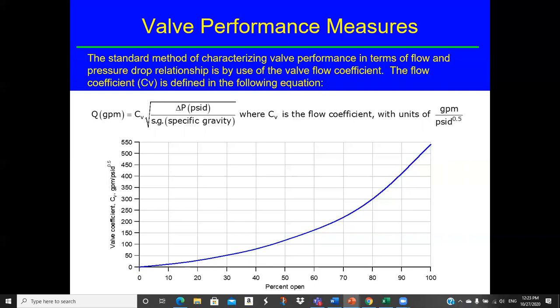But, you know, when you're working with pinch valves, going to the manufacturer, getting the actual valve model number, and getting the appropriate curve of CV versus position is very, very helpful and a very common practice. You will also notice that at 100% open, this valve has a characteristic CV of, I'd say, 540. And so that allows you to calculate a projected pressure drop when the valve is wide open. The fact that the valve is installed at all, even if you're not trying to pinch the flow, there'll still be some pressure loss just due to the fact that the flow has to go through the valve in its wide open position.